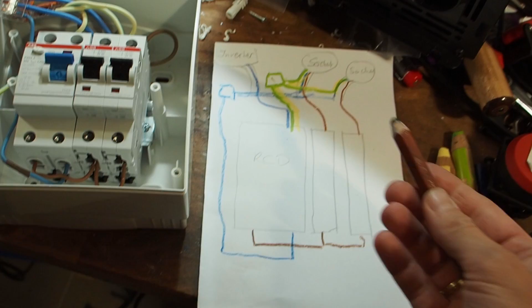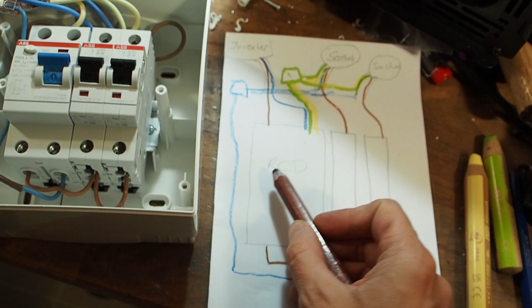Okay, hold on a second, I forgot one cable. Of course, we also need to connect the inverter here to the RCD. Oh yeah, and there's one more thing - there's one more cable coming from the inverter. It's another ground cable, but because the inverter isn't giving out a true ground, I just taped it off. I tucked it to the side here because you're not going to need it, since we've made a new ground wire.